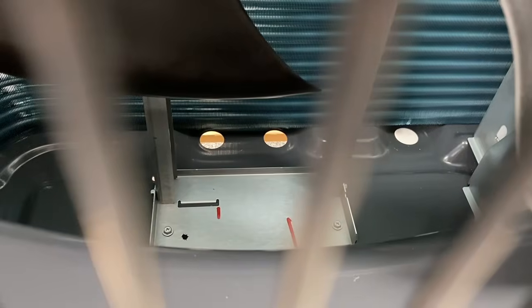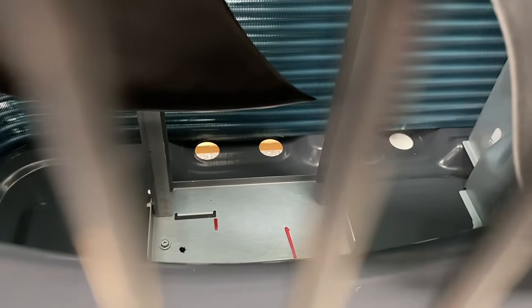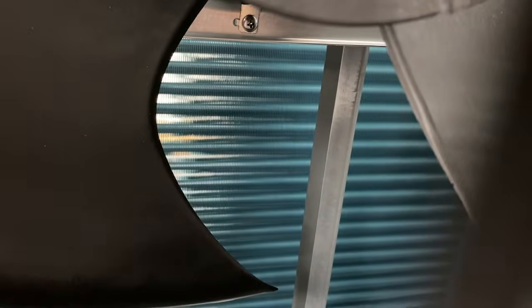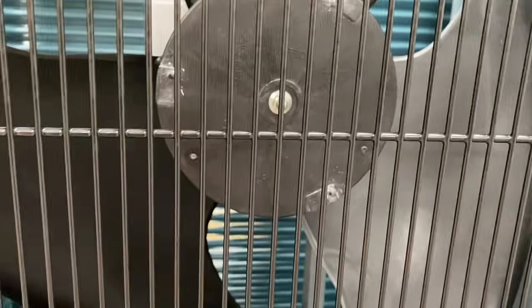I'll also point out there's a couple of holes right at the very back there. If it focuses in, we will connect a condensate drain to that. Basically, all that pipe work at the back there gets very, very cold and starts to form a little bit of ice around it. When it gets to a certain temperature, the heat pump then has to go into a defrost. When it starts to defrost, it draws the heat back in through the refrigerant gas and through the refrigerant tubes. It gives it a chance to melt the ice that would be formed. It shouldn't be a huge amount, but in the winter time it will be more prominent, and then that will need to drain away. We put that to a drain or a little soak away. You can have a shingle base underneath that will allow the water to run away. Just to point that out too.